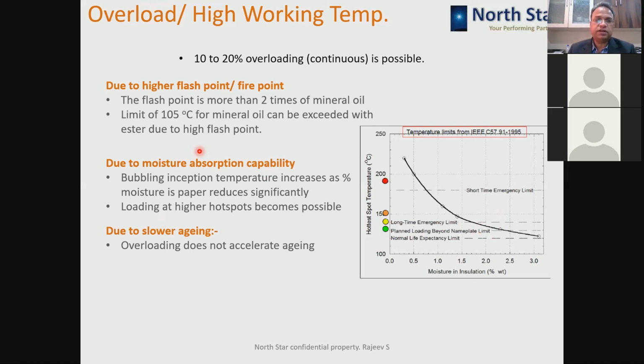If you use synthetic or natural ester, because of their high moisture absorption capability, the moisture in the environment is very little, so the bubbling inception temperature will be very high. Okay, the third property which makes the transformer capable of taking overload is slower aging. Since overloading does not accelerate aging, you are not worried that you are eating away your transformer faster. So your transformer will slowly age compared to a mineral oil transformer.